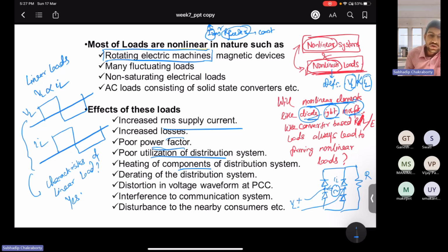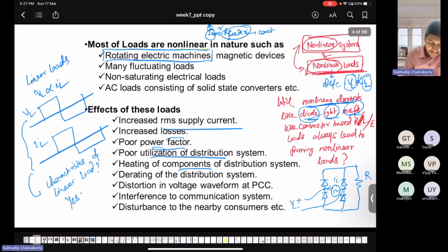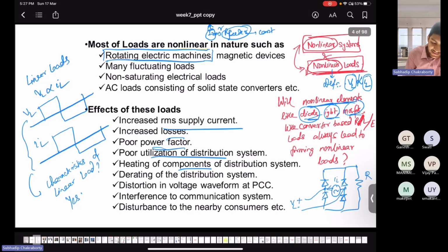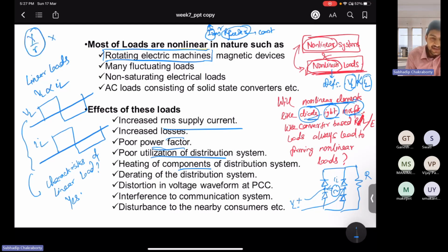The line impedance keeps on increasing, and when you have an AC grid with a comparable X by R ratio, obviously X should be greater than R of the line, but amplitude-wise mod X and mod R are high. Then the impedance of the grid also becomes high. And where are they prevalent? In long transmission lines, long feeders, in remote locations.